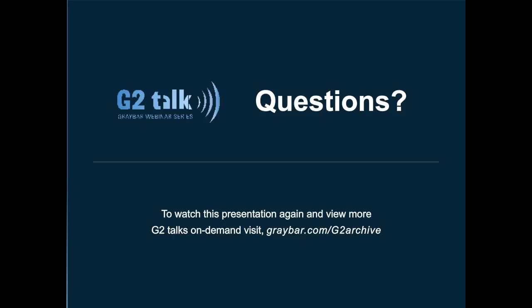So when you're talking about maintenance standards in NFPA 70E, you're really talking about the abnormal conditions. A junction box, once installed and everything's closed up, is good. The contractor did it correctly, a code inspector comes through and checks off on the facility, and the facility has occupancy and you can use it. But when you talk about actually maintaining things, you're not going to typically do your troubleshooting at a junction box. Your troubleshooting is going to be at your disconnect switches, your panel boards, your control centers. You've got to open those up, change a circuit breaker, change a fuse. If you've got a control panel on an assembly line, you've got to do your testing for different voltages at that location. But the junction box should be secured, should be closed, and any time you're going to be doing any work to that system, you should be shutting power off there.